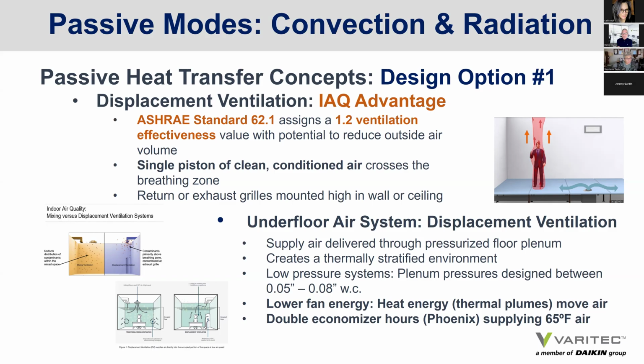Underfloor air systems also offer the promise of a thermally stratified environment. They can be designed to provide displacement ventilation to a space and to create a thermally stratified environment. The difference here is that instead of using low in-wall diffusers, a pressurized plenum floor is used with diffusers mounted into it, and air from that plenum at low pressure, at 0.05 to 0.08 inches, injects air into the space to allow for that thermally stratified environment to be created. So at these lower pressures, underfloor air systems offer an added level of efficiency to displacement ventilation. Also, because these systems supply warmer air, as mentioned earlier, at 65 degrees, there's another level of efficiency added by doubling economizer hours, certainly in our Sonoran desert climate.